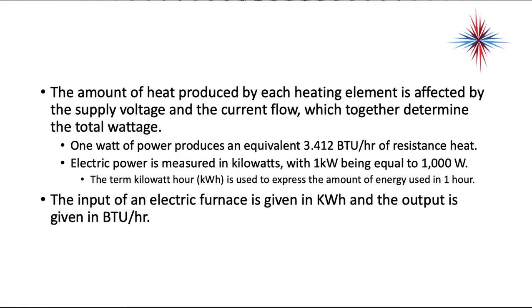The amount of heat produced by each heating element is affected by the supply voltage and the current flow, which together determine total wattage. 1 watt of power produces the equivalent of 3.412 BTUs per hour of resistive heat. Electric power is measured in kilowatts, with 1 kW being equal to 1,000 watts. The term kilowatt hour is used to express the amount of energy used in 1 hour. So 1,000 watts produces 3,412 BTUs per hour of heat. The input of an electric furnace is given in kilowatts, and the output is given in BTUs per hour.